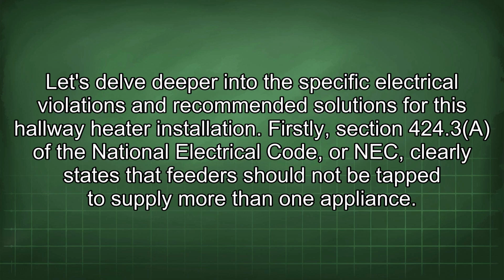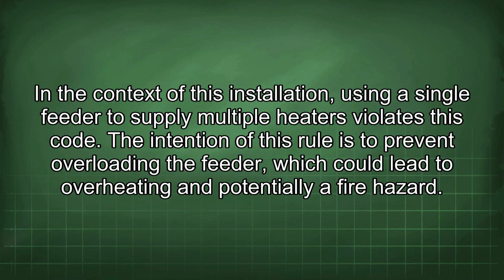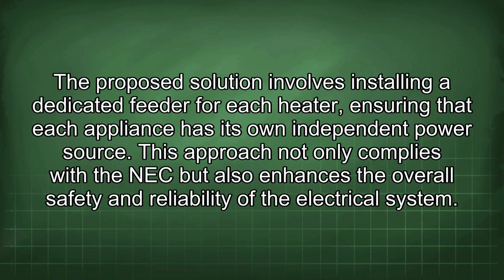Firstly, Section 424.3 of the National Electrical Code, or NEC, clearly states that feeders should not be tapped to supply more than one appliance. In the context of this installation, using a single feeder to supply multiple heaters violates this code. The intention of this rule is to prevent overloading the feeder, which could lead to overheating and potentially a fire hazard. The proposed solution involves installing a dedicated feeder for each heater, ensuring that each appliance has its own independent power source. This approach not only complies with the NEC but also enhances the overall safety and reliability of the electrical system.